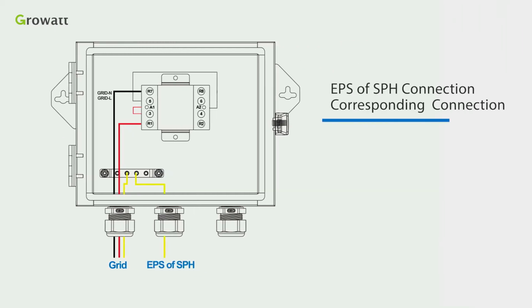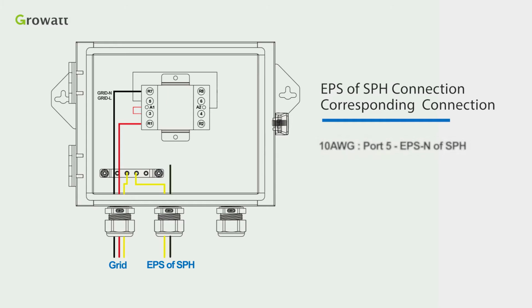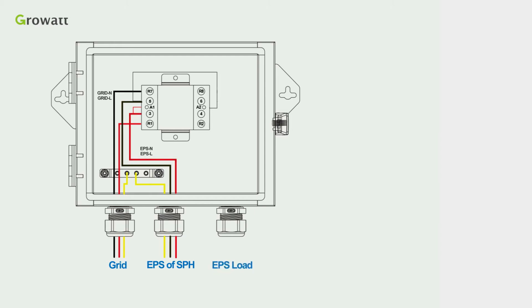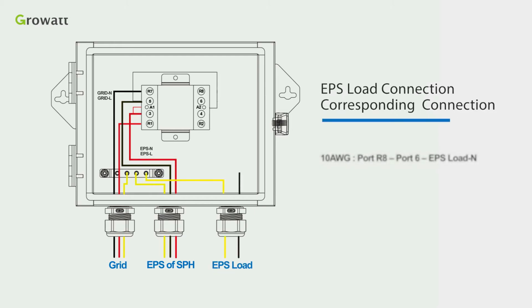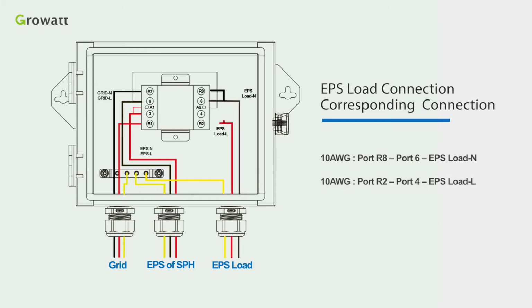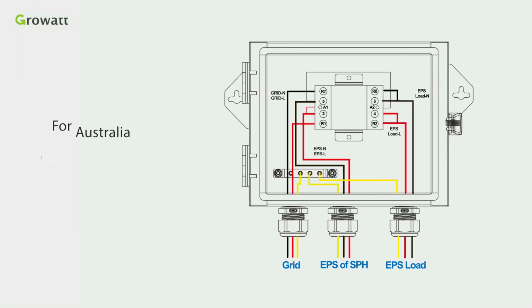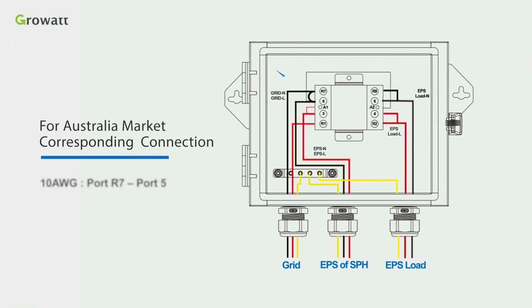Secondly, for EPS of SPH connection, use the 10 AWG cable to connect the port 5 and EPS-N of SPH, and the other 10 AWG cable connect the port 3 and EPS-L of SPH. Thirdly, for EPS load connection, use the 10 AWG cable to short port R8 and port 6 and connect to the N line of the EPS load, and use the 10 AWG cable to short port R2 and port 4 and connect to the L line of EPS load finally. That's the complete connection of Standard 1. For the Australia market, you still need to short the port R7 and port 5 based on the Standard 1.